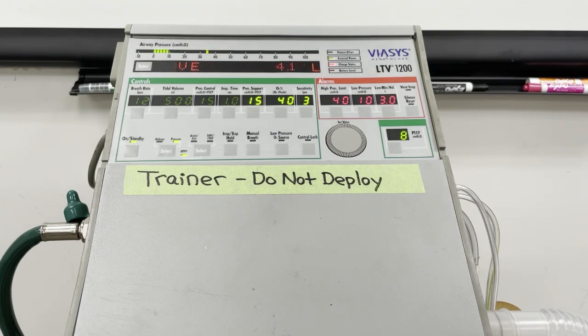If you had dialed pressure support to 15, that would have been an error. How much PEEP would be delivered then? When you factor in the EPAP value, it comes out to 23. 23 centimeters of water pressure. Earlier, I told you when we take a breath, our lungs pressurize to about 20 to 25 centimeters of water pressure at the peak of inspiration.